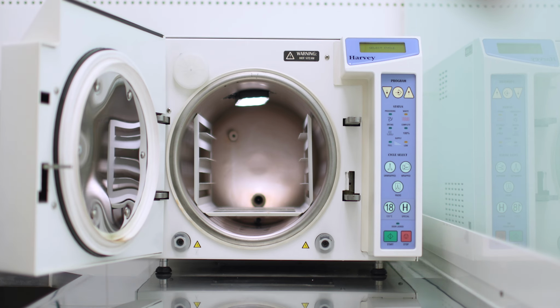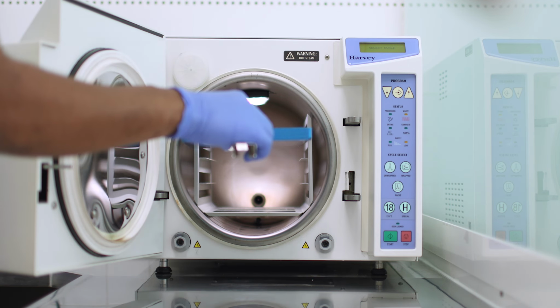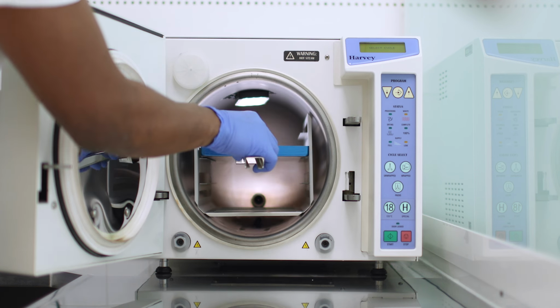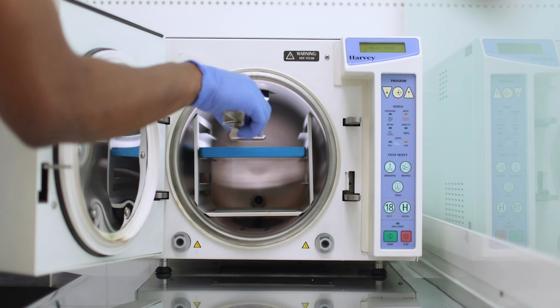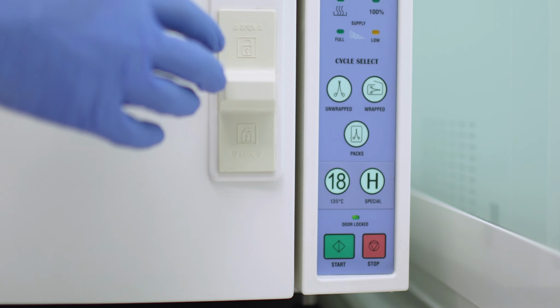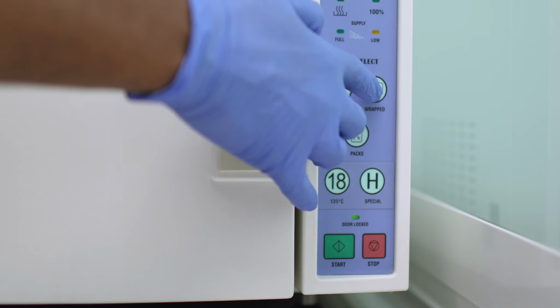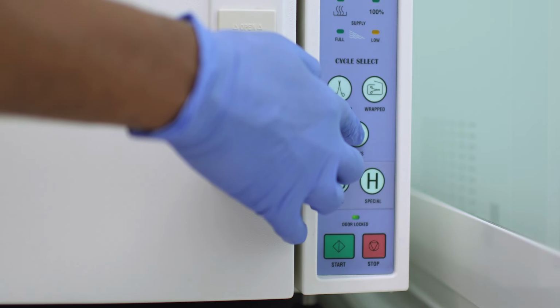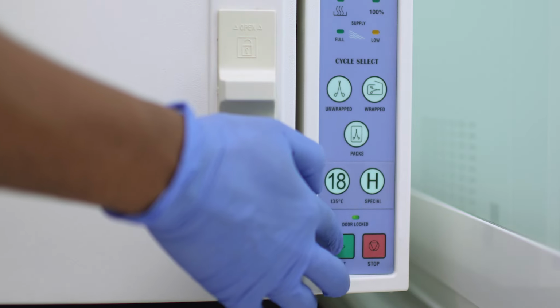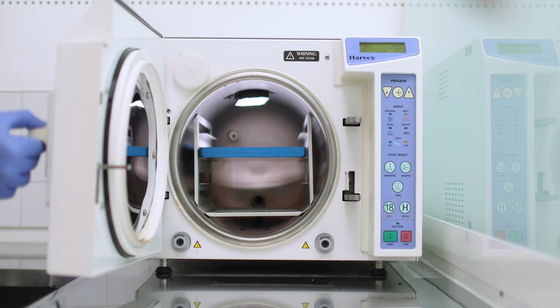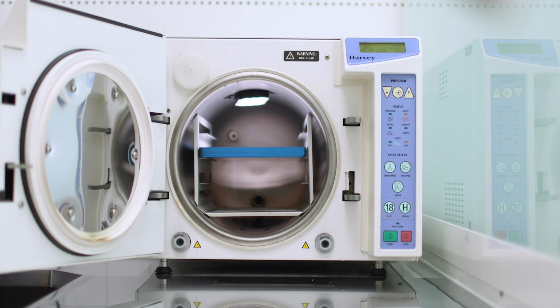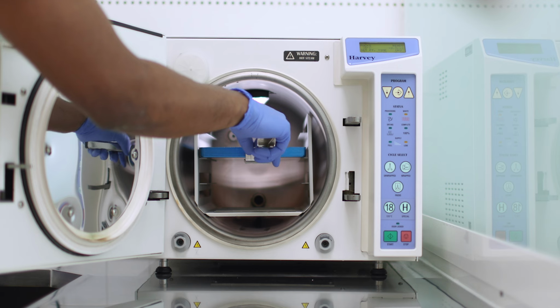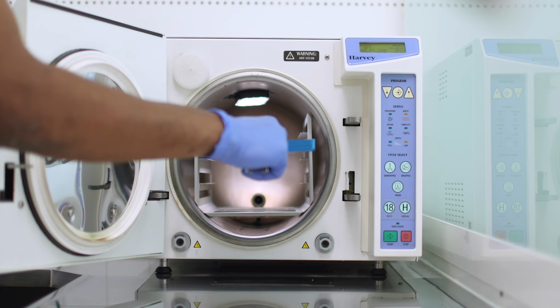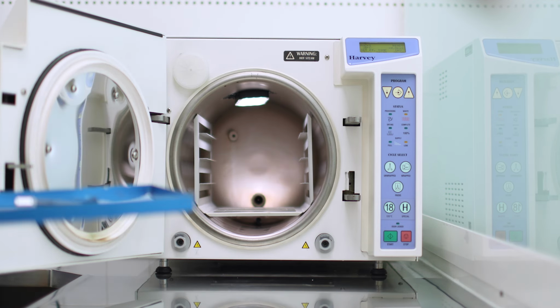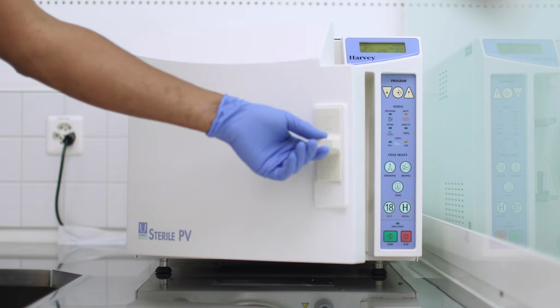Thorough cleaning and disinfecting of the light guide is imperative to ensure that its subsequent sterilization is effective. For this purpose, use only autoclave sterilization with the settings of 3 times pre-vacuum and a sterilization time of 4 minutes at 134 degrees Celsius. The pressure during the sterilization should be 2 bar. For further information and more detailed instructions, please refer to the instructions for use.